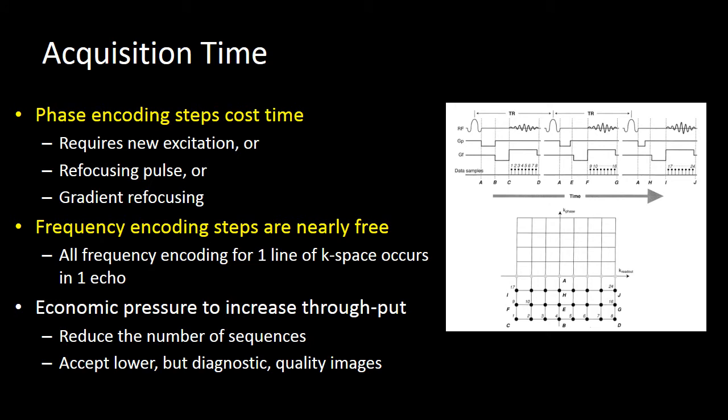Let's think about how phase-encoded steps cost time. For each line of k-space, we require a different phase gradient and therefore a separate RF pulse to create each line of k-space. Frequency-encoded steps are almost free because all we do is change either how much of an echo we sample or how rapidly we sample that echo. We can change our frequency-encoded field of view or resolution just by changing our sample rate and the time or extent that we sample the echo.